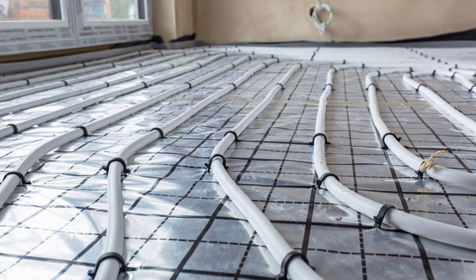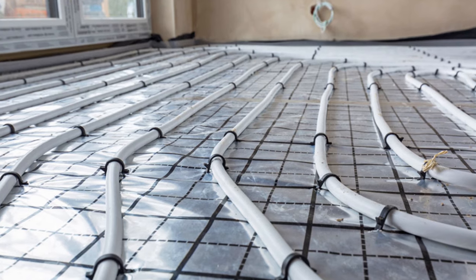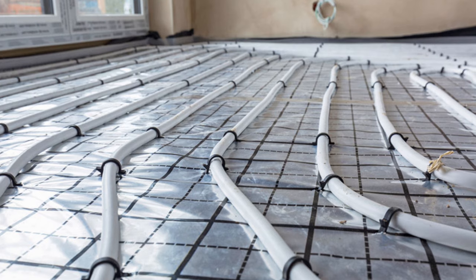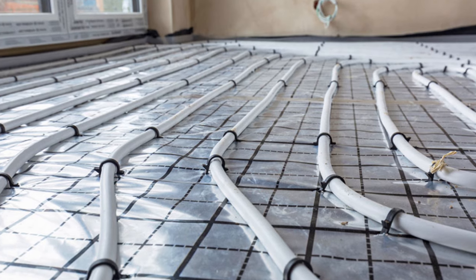Once we have our two inches of insulation down over our four inches of gravel subbase, I'm going to put a 10-mil plastic vapor barrier over top. That will make sure that no ground moisture can work its way up into the slab. Then on top of that vapor barrier, I'm going to be running all of my circuits of half-inch PEX tubing. I'll be using PEX staples to fasten that tubing down in evenly spaced circuits about one foot on center. Half-inch tubing has a six-inch bend radius.